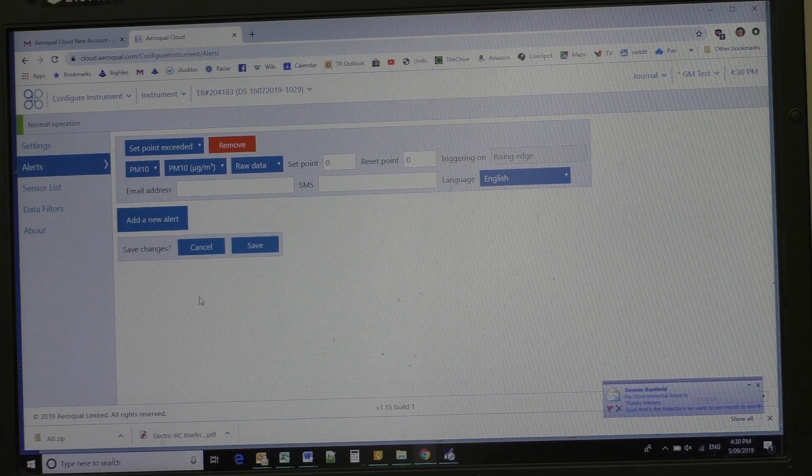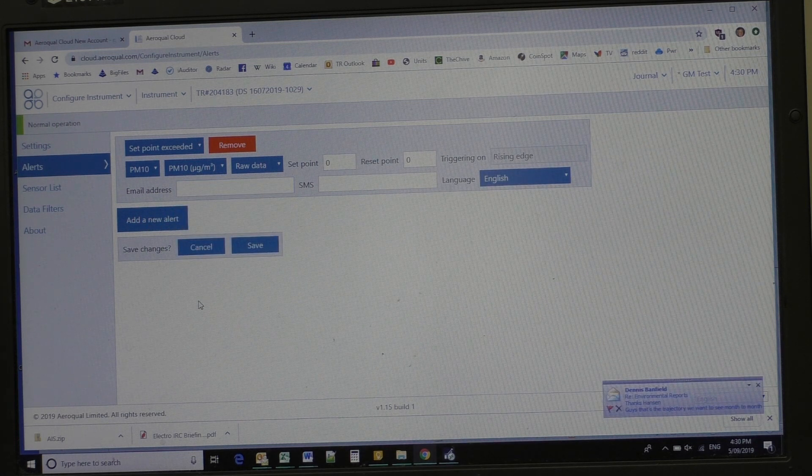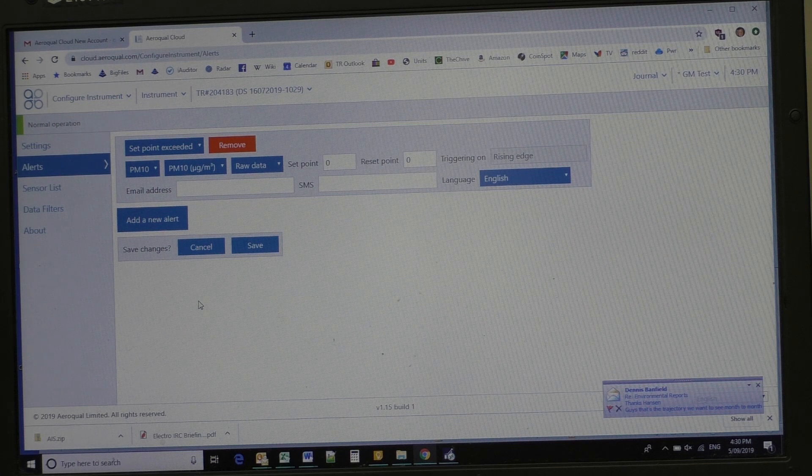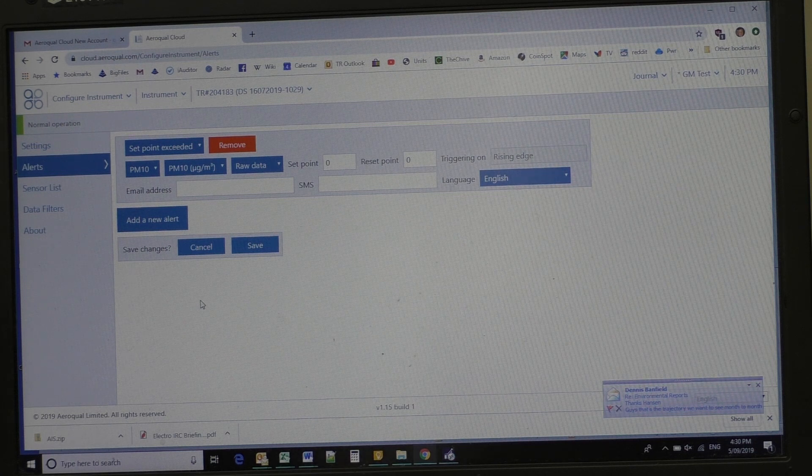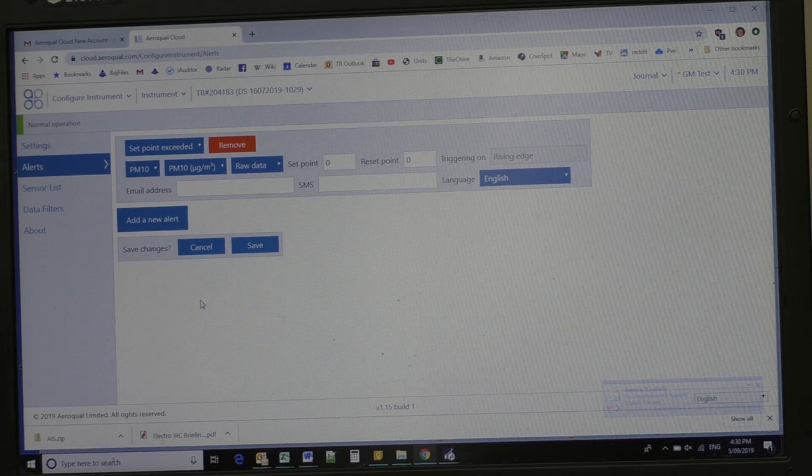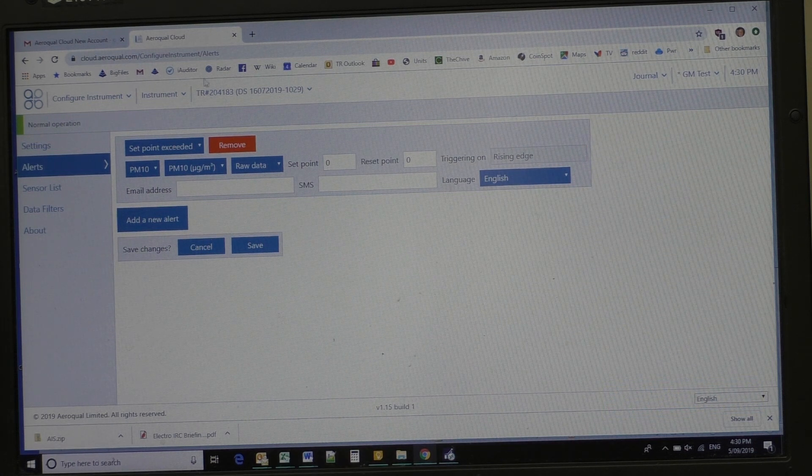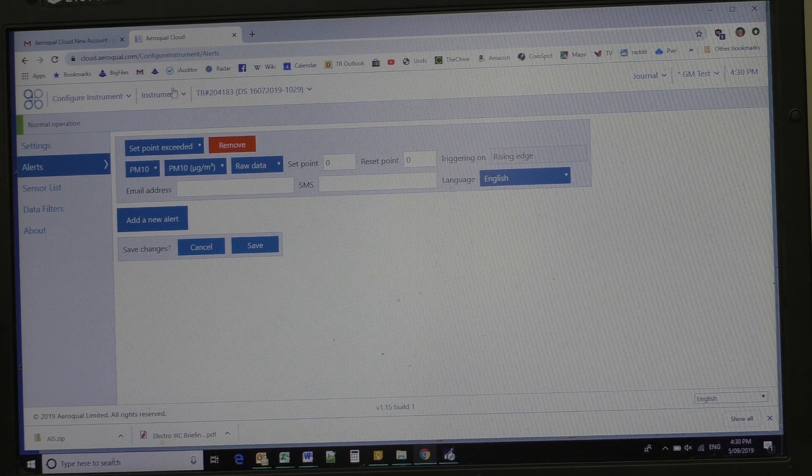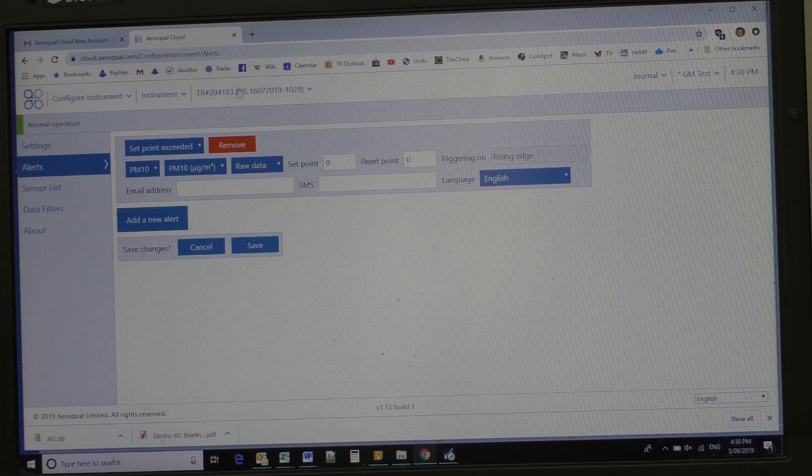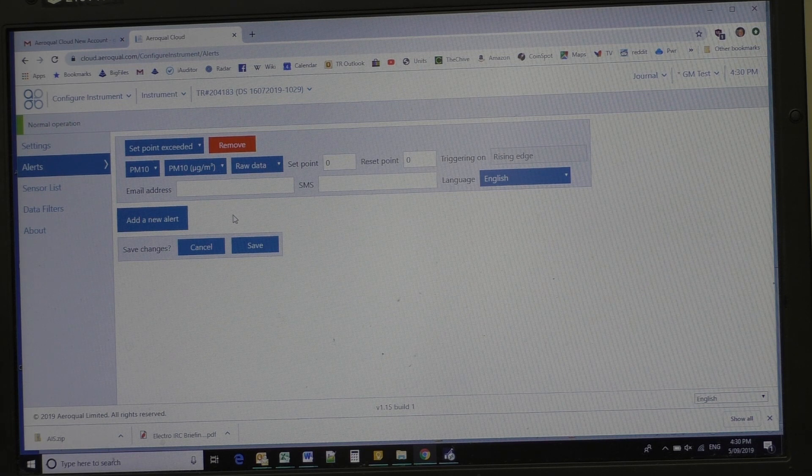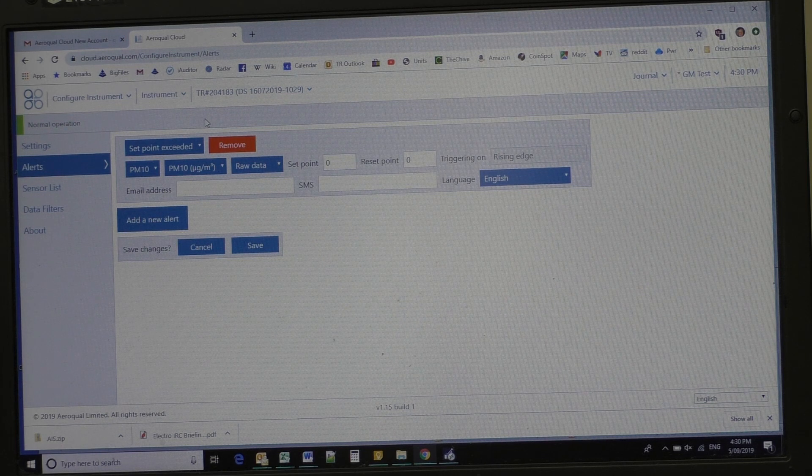You have multiple alerts at multiple levels, if you want to when the dust levels come up too high, for each instrument. So you can configure those separately or together.